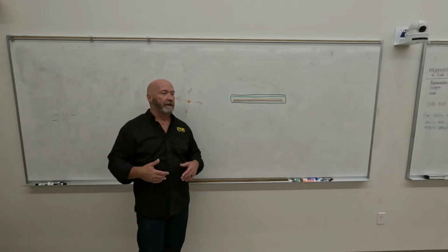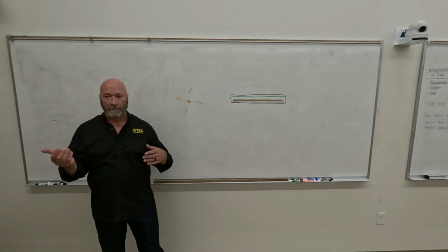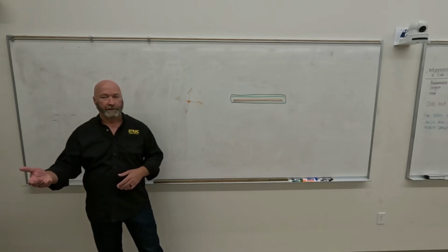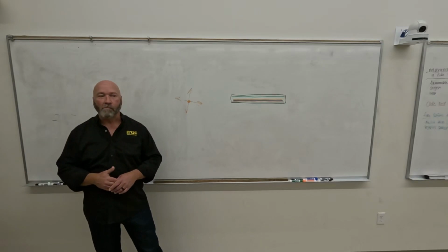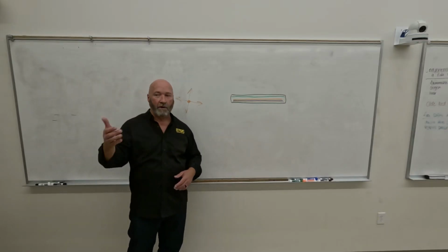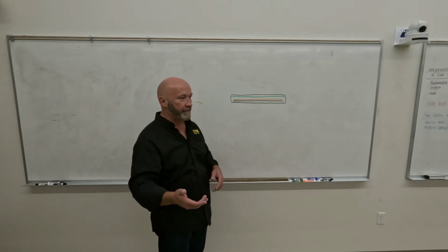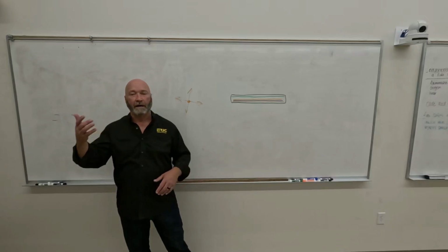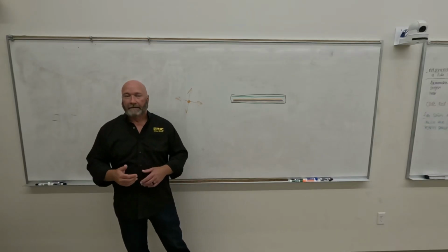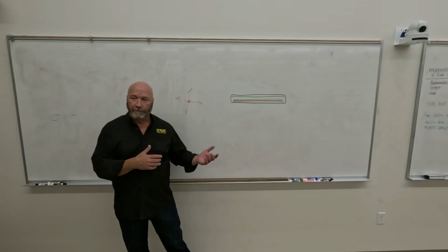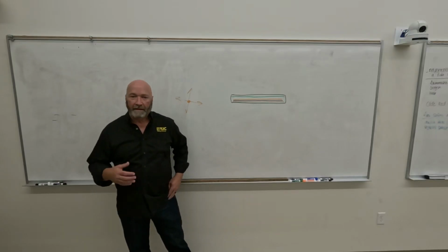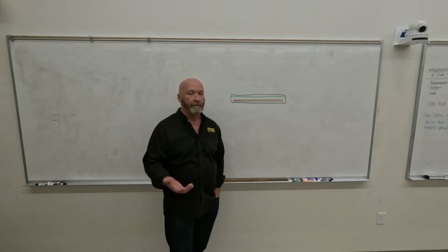What you're left with is a more high energy x-ray beam. Those low energy photons go away. So what is the purpose of filtration? To stop the low energy x-ray photons. File this away: it hardens the x-ray beam. A hardened x-ray beam is one where you have fewer low energy x-ray photons and more high energy x-ray photons. So a hardened beam, with those low energy photons removed, leaves us with a safer beam. And then he also invented beam restriction.